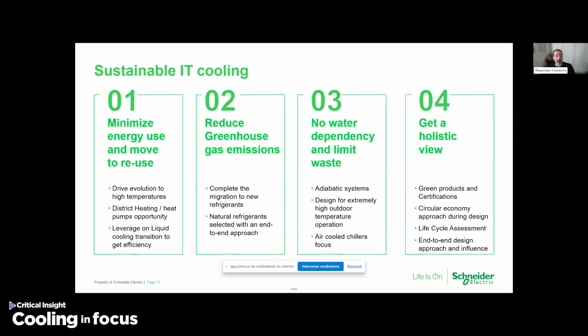So minimize energy use, definitely. We need to reduce energy consumption, use free cooling as much as we can, leverage high temperature design for a data center according to ASHRAE recommendations - 27 degrees C discharge at minimum, 22 to 23 degrees C at the chiller side. Try to have district heating, as discussed in a previous conversation at this event.